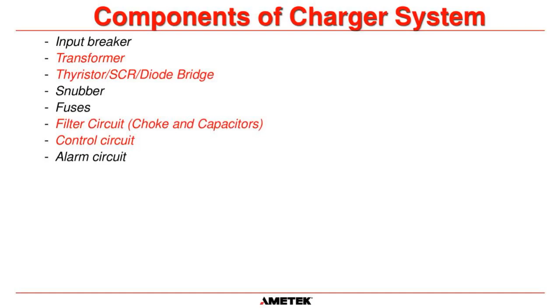Here is a very simple single line diagram of a charger taken from one of our DCR chargers that we sell. On the left-hand side is your AC input - usually three-phase 480 volts in the US, maybe 600 volts in Canada. That goes through an AC input breaker, then through a transformer, which steps that 480 down, and then that goes into the charger portion or the rectifier bridge.